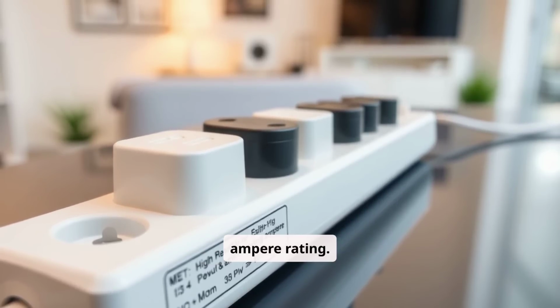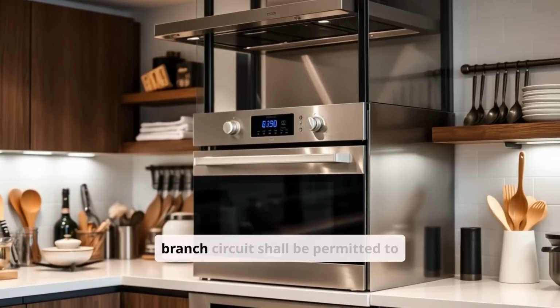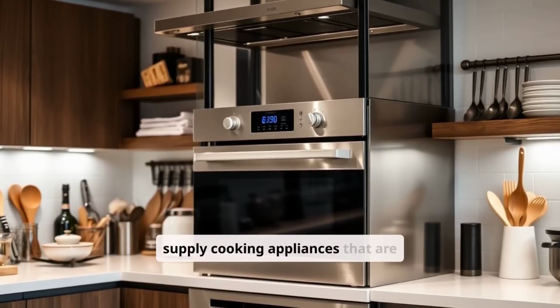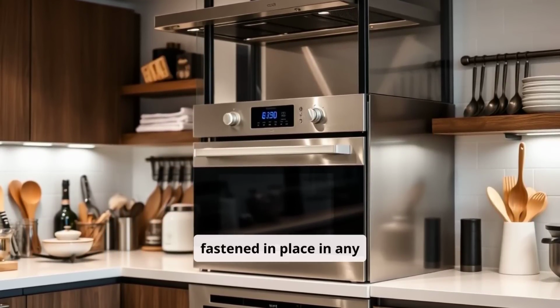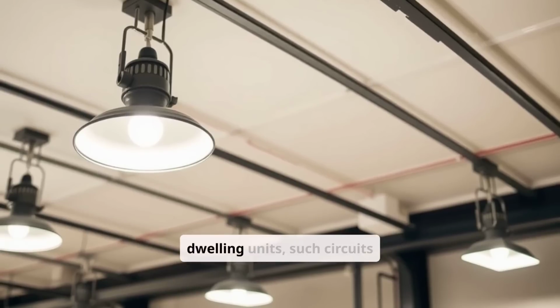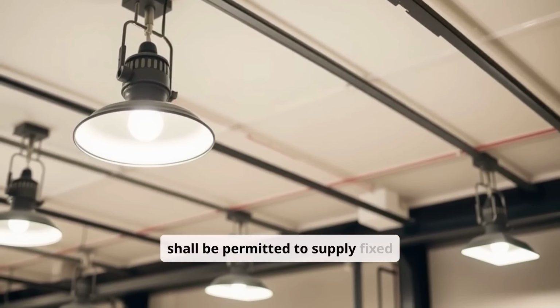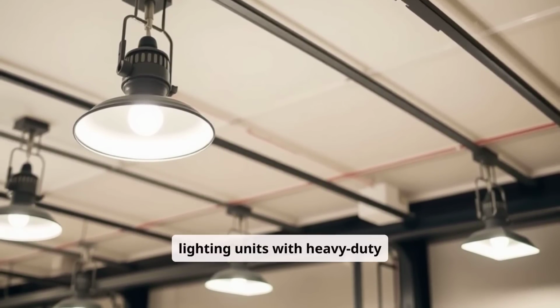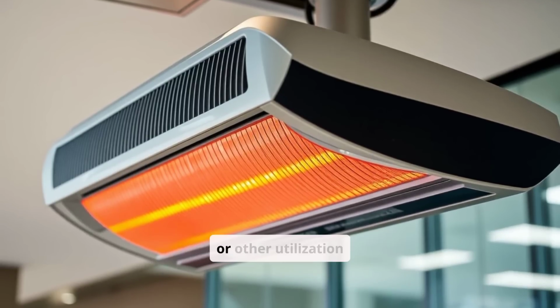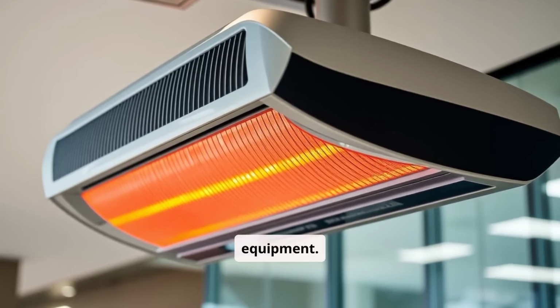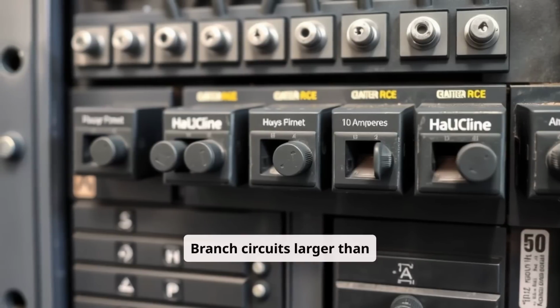rating. A 40 or 50 ampere branch circuit shall be permitted to supply cooking appliances that are fastened in place in any occupancy. In other than dwelling units, such circuits shall be permitted to supply fixed lighting units with heavy-duty lamp holders, infrared heating units, or other utilization equipment. Branch circuits larger than 50 amperes shall supply only non-lighting outlet loads.